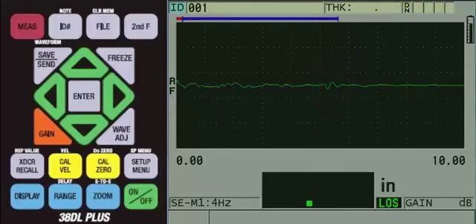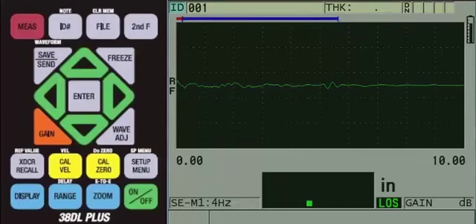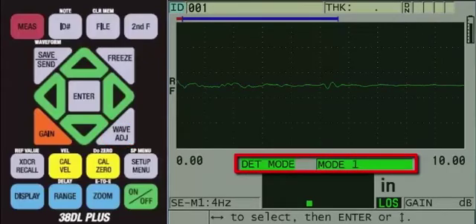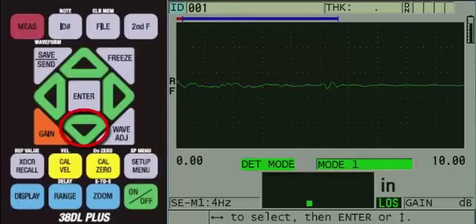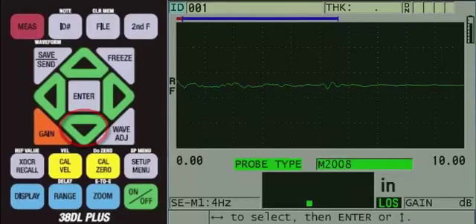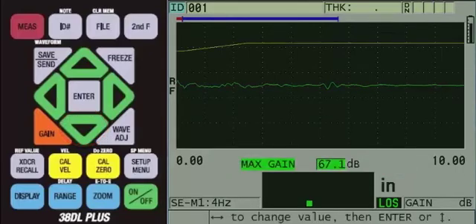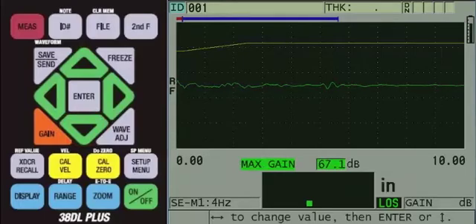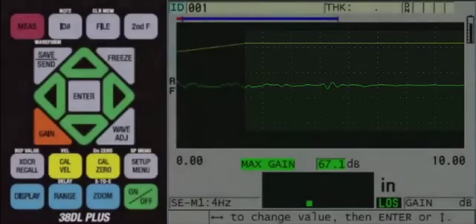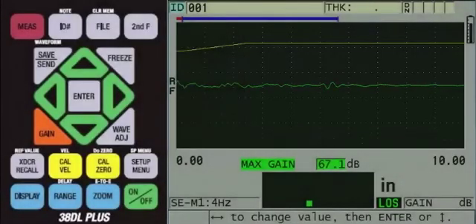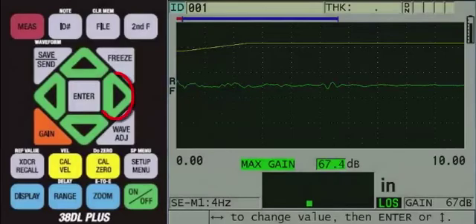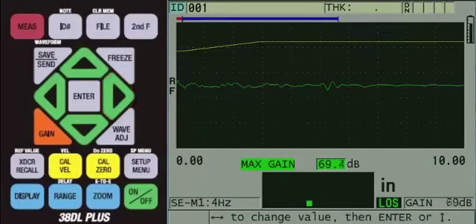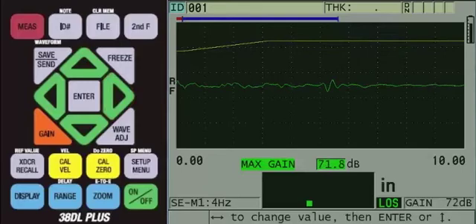Since the signal is too low in amplitude to be measured, we need to increase the gain. To do this, press the WAVE ADJUST key. This will bring up the setup parameters at the bottom of the screen. Press the down arrow to the GAIN settings. Once you get to MAX GAIN, you will see the yellow GAIN line, which identifies which of the three GAIN settings need adjustment. Since the back wall echo is under the MAX GAIN portion of the GAIN line, we need to increase the MAX GAIN. Use the right arrow to increase the MAX GAIN. Increasing the MAX GAIN will also adjust the TDG slope.